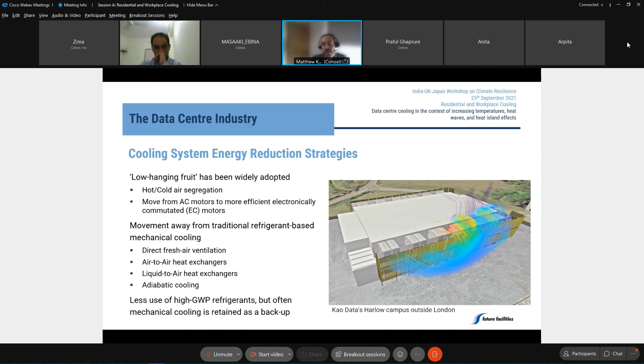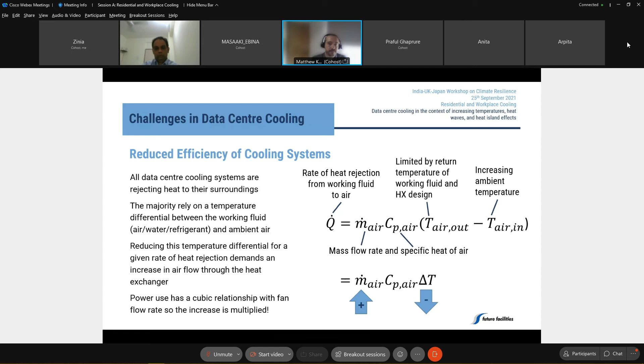So to reject heat to their surroundings, all of the cooling systems I've mentioned rely on a temperature differential between the working fluid and the ambient air. This is the case whether the working fluid is air, water, or refrigerants. And the temperature at which air can leave the heat exchanger that's rejecting the heat to atmosphere is limited both by the temperature of the working fluid entering the heat exchanger and by the design of the heat exchanger. So as the ambient temperature increases, the possible increase in air temperature through the heat exchanger is reduced, and so is the amount of heat that can be transported away per unit mass of air. And so for a fixed rate of heat rejection, as the air temperature delta reduces with increasing temperatures outside, we actually have to increase the mass flow rate of air through these heat exchangers. And that, of course, means increasing fan speeds to increase the fan flow rate. And as a result of fan laws, the power use actually increases with a cube relationship to fan speed.